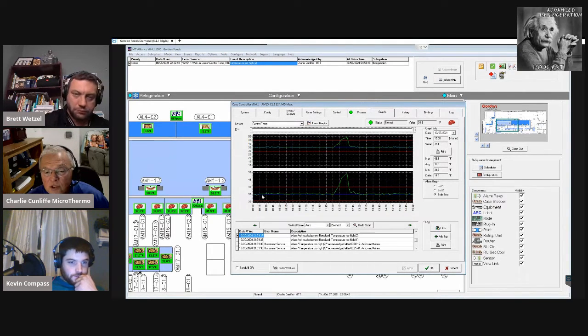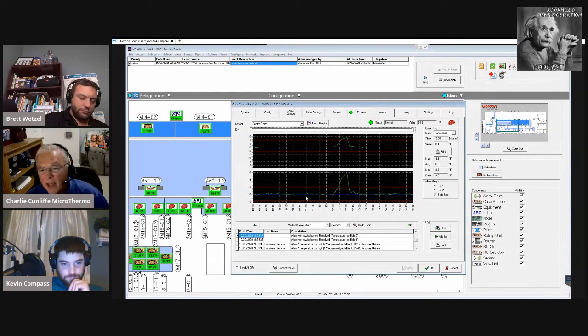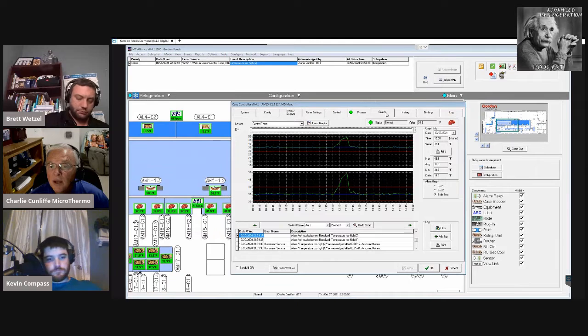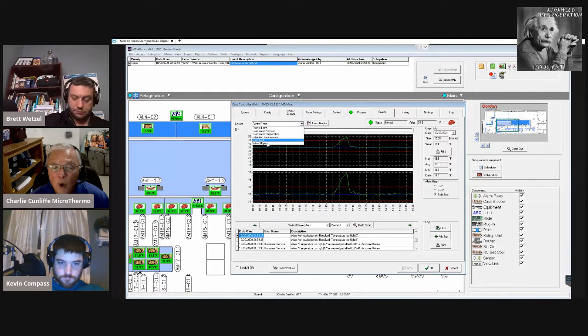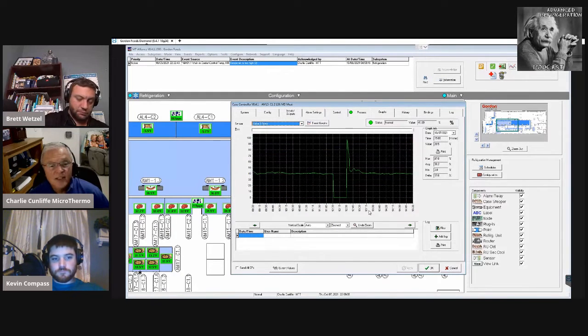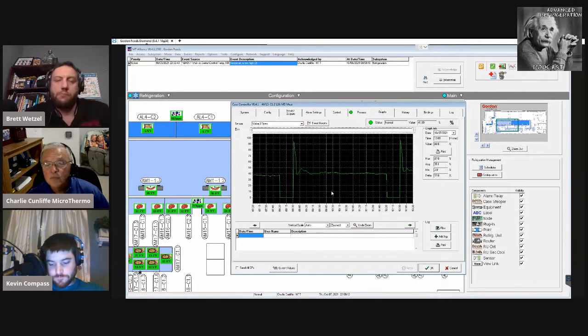The blue is the set point, and the green is the actual temperature. So you see this case controller is working tight. If somebody doesn't do their due diligence, this can be super spiky and all over the place. But again, what are some of the things I would do to tighten up? I would go into graphs, and I would go into valve position. So let's go percent valve open. So you see that? Look at that. Whoever is doing this store, they got this right on the money.